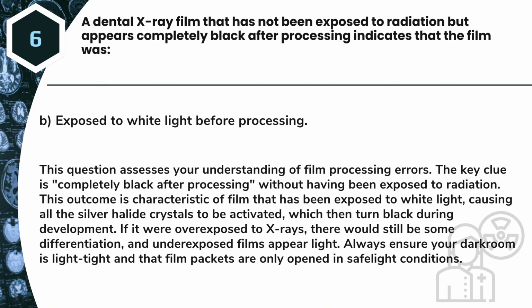If it were overexposed to X-rays, there would still be some differentiation, and underexposed films appear light. Always ensure your darkroom is light-tight and that film packets are only opened in safe light conditions.